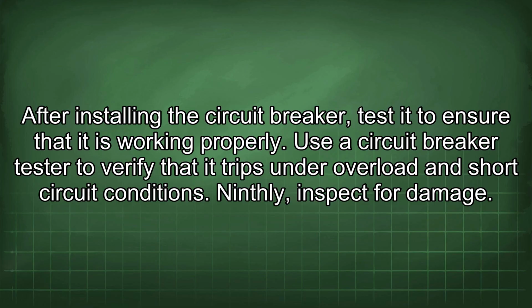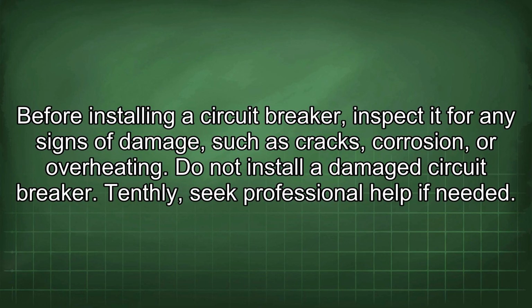Ninthly, inspect for damage. Before installing a circuit breaker, inspect it for any signs of damage, such as cracks, corrosion, or overheating. Do not install a damaged circuit breaker.